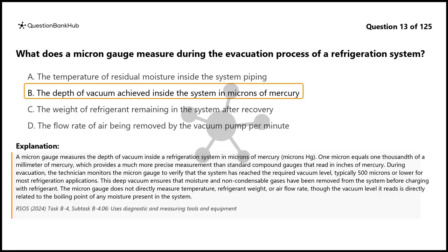During evacuation, the technician monitors the micron gauge to verify that the system has reached the required vacuum level, typically 500 microns or lower for most refrigeration applications. This deep vacuum ensures that moisture and non-condensable gases have been removed from the system before charging with refrigerant. The micron gauge does not directly measure temperature, refrigerant weight, or air flow rate, though the vacuum level it reads is directly related to the boiling point of any moisture present in the system.